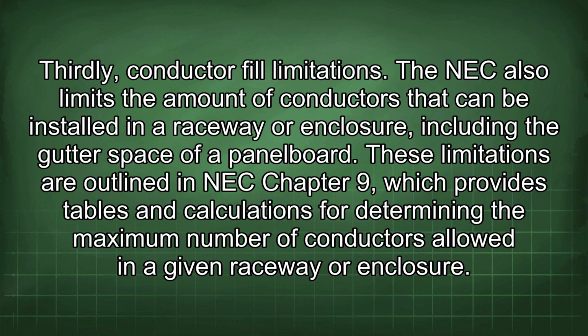Thirdly, conductor fill limitations. The NEC also limits the amount of conductors that can be installed in a raceway or enclosure, including the gutter space of a panel board. These limitations are outlined in NEC Chapter 9, which provides tables and calculations for determining the maximum number of conductors allowed in a given raceway or enclosure.